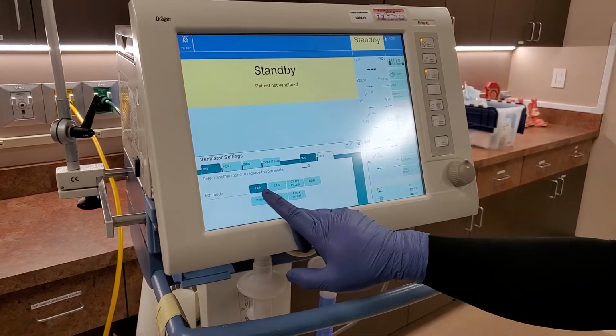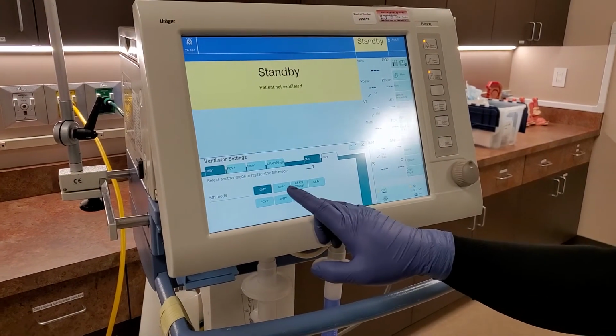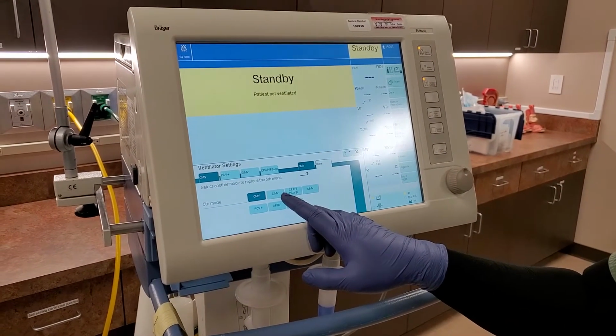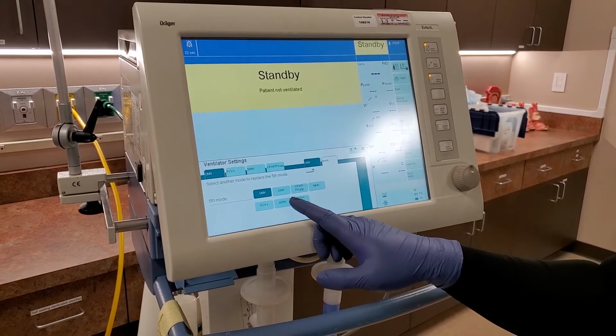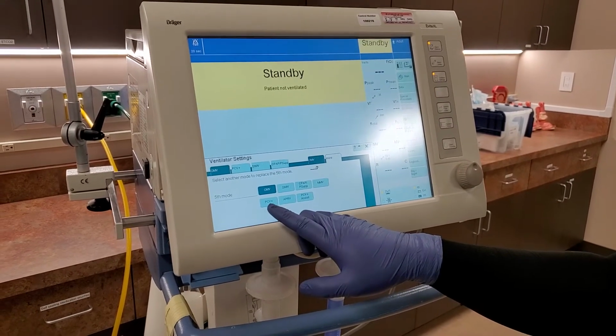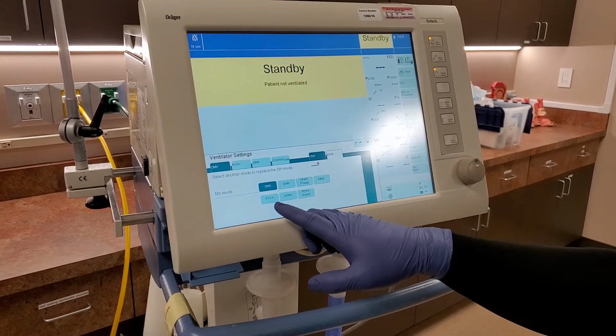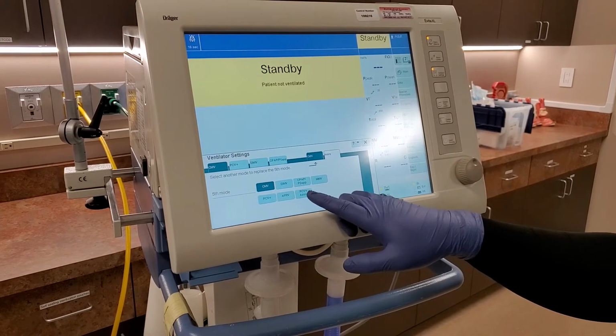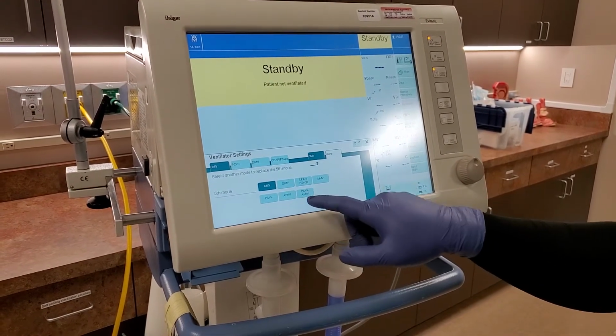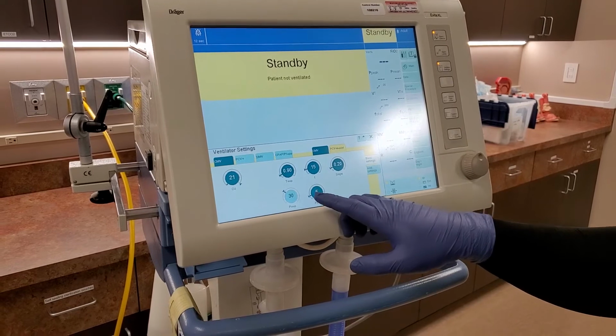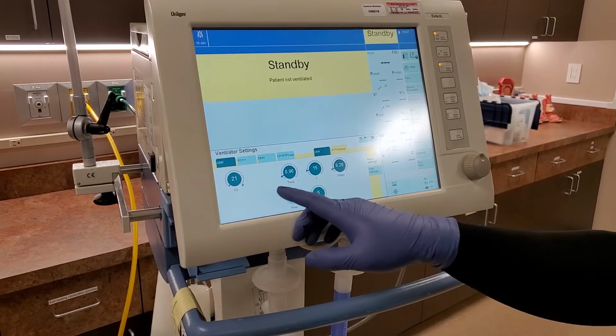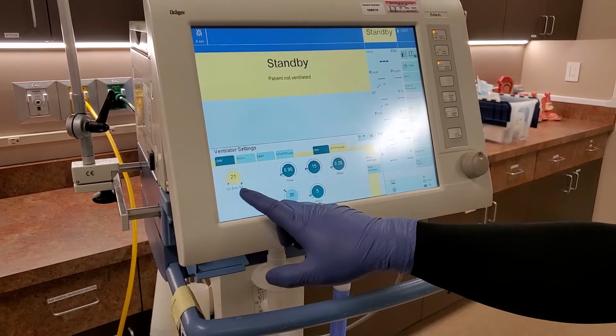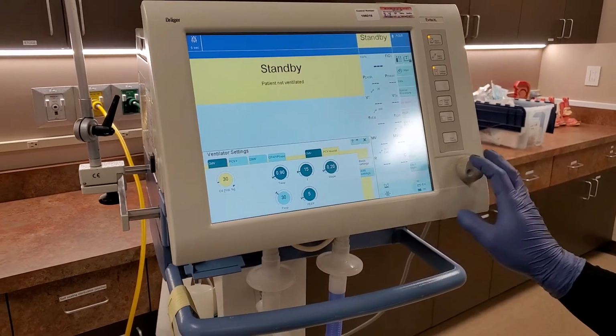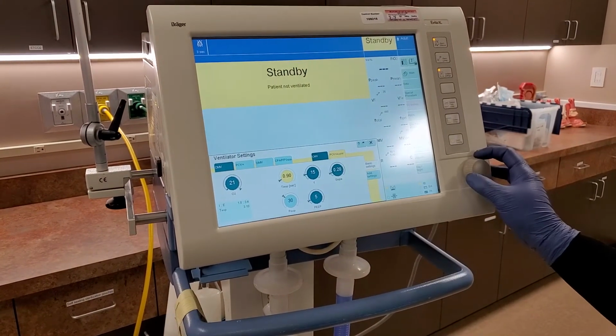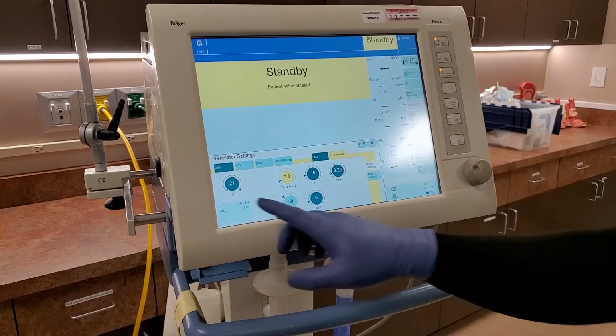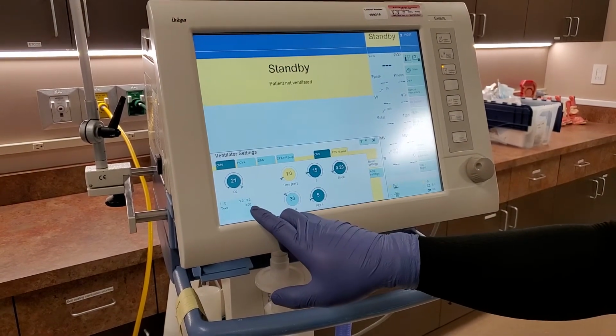So CMV is ACVC, SIMV is SIMV with volume control, PCV plus is SIMV with pressure control, and then PCV plus assist is actually ACPC. So we'll pick a setting here. So here you pick your FiO2 percentage. We'll go to 30, you got your Ti time. We'll put it to 1 and you can actually see their IE ratios here.